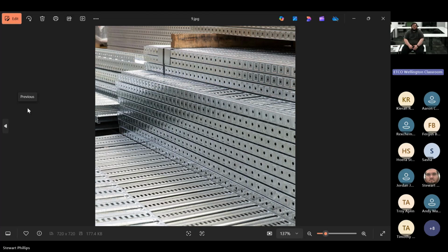Do we need to do seismic bracing? Any drop over 400 mil, we need to do seismic bracing, or at least that's what it was at the hospital, I believe. There is a certain requirement for mechanical. But if the threaded rod coming down from the ceiling is too long, you need to brace it. And then you'll also need to do seismic strapping as per the engineer's drawings.